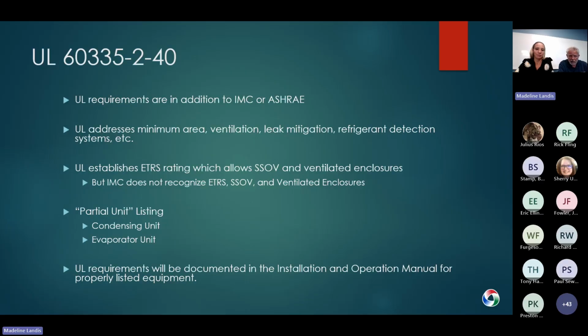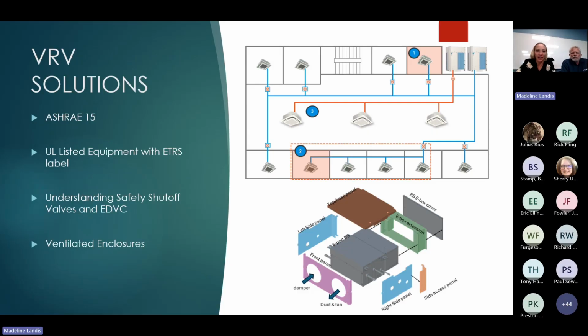We have a few solutions we can talk about, but this all should be documented in the IOM manuals, the operations and installation manuals, and therefore you really need to be reading up on these along with the product selections we're getting you. So then we can move on into some of those solutions. Like Mark mentioned, it's our recommendation to really focus on ASHRAE 15 in lieu of IMC to avoid having to use those ventilated, fire resistive piping shafts in VRV designs. First and foremost, another way to make sure that the product is going to meet the new code is to select UL listed equipment with the ETRS labels.